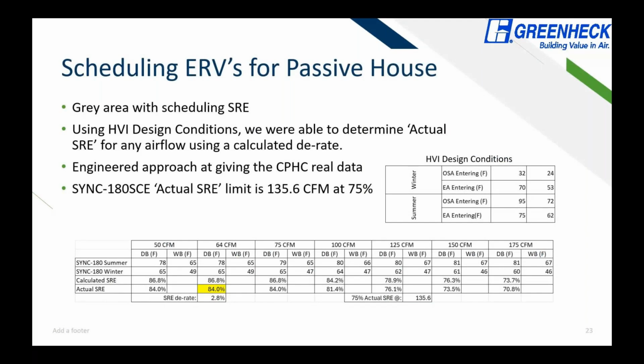So it's important to know that we can, at Buckley, give you the airflow performance with a pretty good guess of what that actual SRE is for any airflow or design condition, using what we have as a calculated derate. So this is basically our best guess. It's like an engineered approach at giving a CPHC real data. We use the HVI design conditions right here on the right, which is 32 degrees in the winter with its corresponding wet bulb temperature right there. And we developed, using the core simulation data, what the dry bulb and wet bulb temperatures are for each airflow.